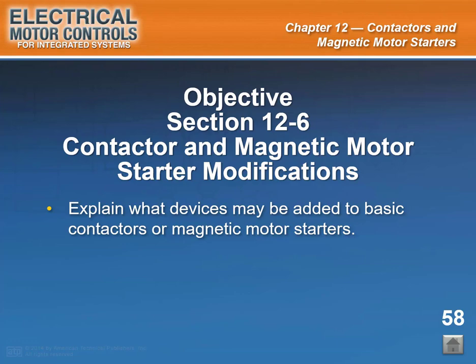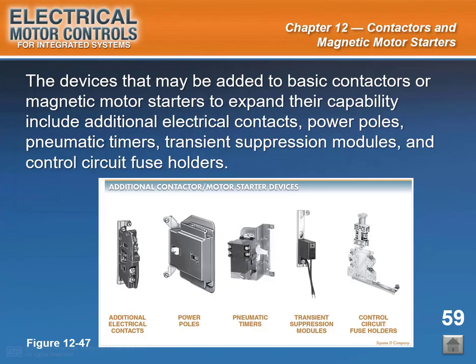Start of slide 59. Slide caption: The devices that may be added to basic contactors or magnetic motor starters to expand their capability include additional electrical contacts, power poles, pneumatic timers, transient suppression modules, and control circuit fuse holders. See figure 12-47 for examples.